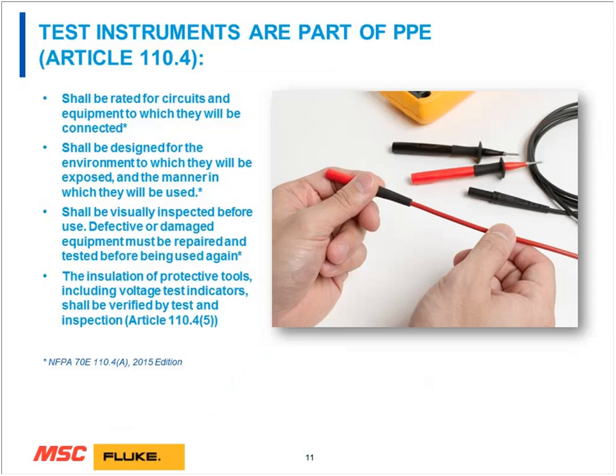There's an article, 110.4 in NFPA, that talks about PPE, and that test instruments are in fact part of PPE. These are printouts from NFPA, but they shall be rated for the circuits and equipment to which they will be connected. What's important is to make sure that the rating of the test leads matches the rating of the environment wherever you're making the measurement. And it's not just the test leads, it's test probes, anything connected to the meter, and the meter itself. They shall be designed for the environment in which they'll be exposed and used in the manner in which they'll be used.